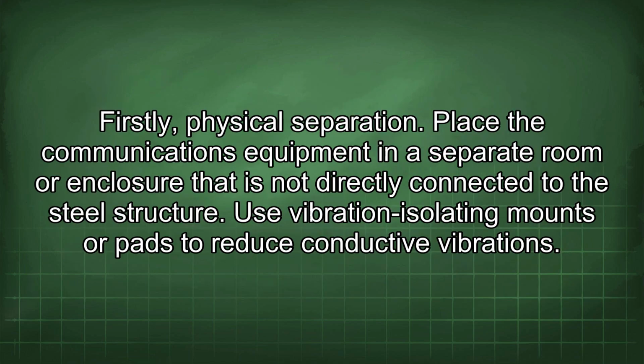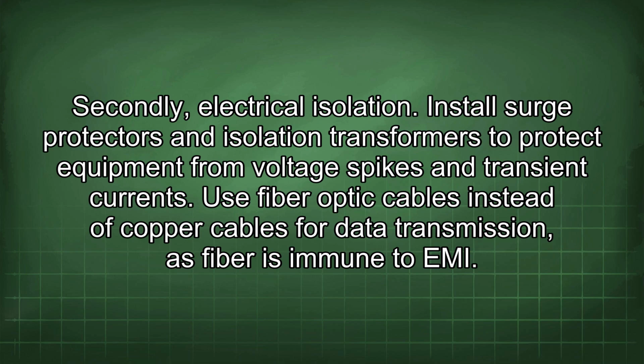Firstly, physical separation. Place the communications equipment in a separate room or enclosure that is not directly connected to the steel structure. Use vibration isolating mounts or pads to reduce conductive vibrations. Secondly, electrical isolation. Install surge protectors and isolation transformers to protect equipment from voltage spikes and transient currents. Use fiber optic cables instead of copper cables for data transmission, as fiber is immune to EMI.